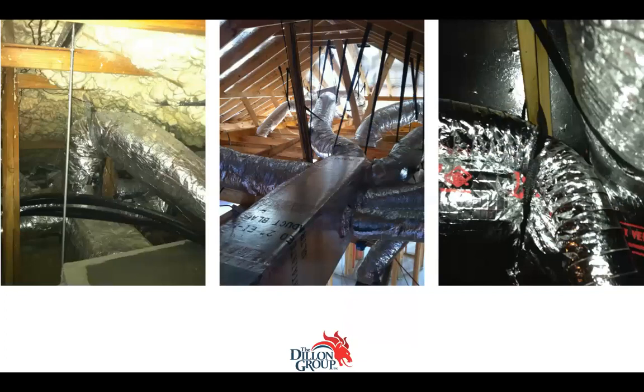So you're talking about the last 18 inches of the duct plenum is not supposed to have any takeoffs. Yeah. That's where this HVAC contractor, the guy in the middle, decided that's where all of them had to be. Right. Well, hey, I like that at least he's got a couple of feet before his first one. He at least did something right. And they're all off the side except for the one feeding the J box at the back. That's interesting.